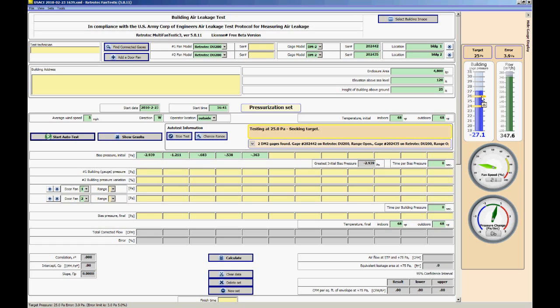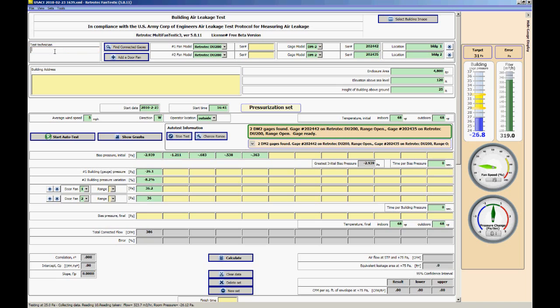The fans that we're using are not particularly easy to control since they have a backward curve impeller. They're a very small fan, so I'm just doing this test in my office. But they do serve to provide a nice test bed, or practice bed, I guess, for doing these tests in real life. I'm just going to pop in technician's name here. You'll notice that your computer's slowed down quite a bit from all the communication that's going on. All this test is being performed, and I'm just going to click on the graphs here.